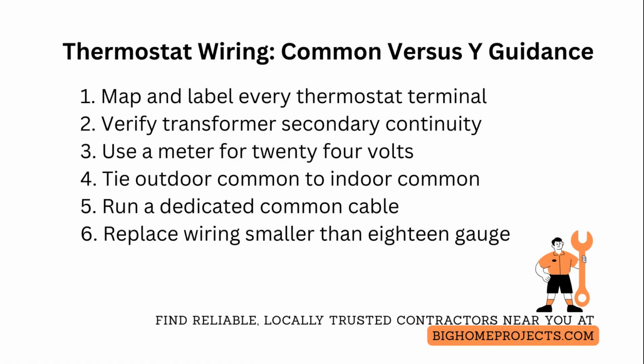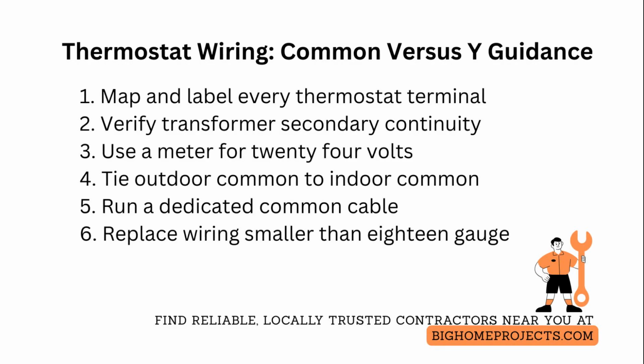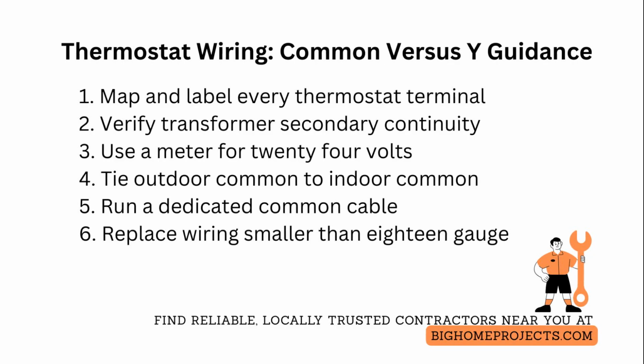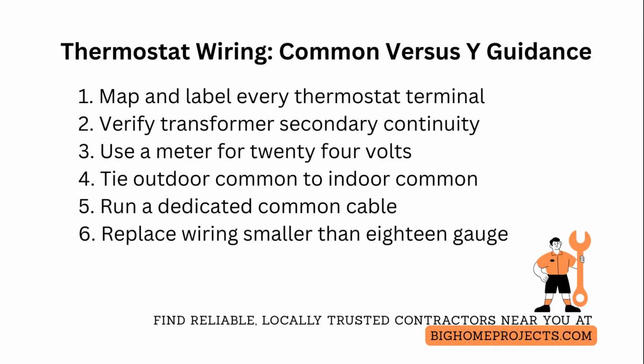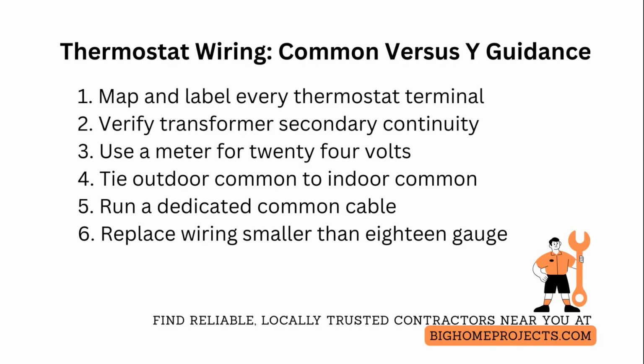Thermostat wiring and replacement requires recognizing that condensing unit control coils are simple electromagnetic devices. They operate on a complete circuit, not polarity, so what matters is a true common reference and a switched call conductor. Test with a multimeter to confirm the conductor labeled Y is actually switching to the outdoor contactor and that the conductor labeled C is a continuous common to the outdoor unit transformer secondary.